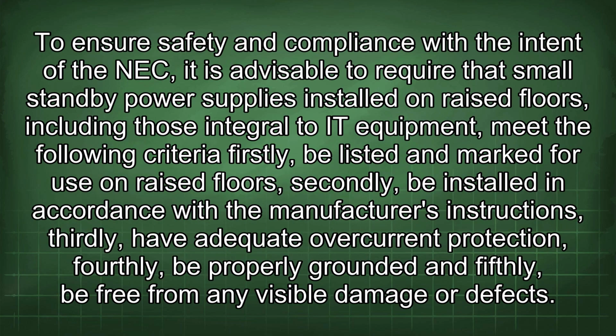To ensure safety and compliance with the intent of the NEC, it is advisable to require that small standby power supplies installed on raised floors, including those integral to IT equipment, meet the following criteria. Firstly, be listed and marked for use on raised floors. Secondly, be installed in accordance with the manufacturer's instructions. Thirdly, have adequate overcurrent protection. Fourthly, be properly grounded. And fifthly, be free from any visible damage or defects.